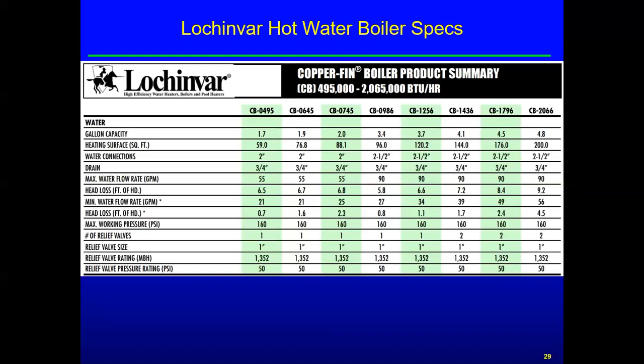Other specs from Lochinvar: head loss is what you use for sizing the pump — what's the pressure drop across the boiler? You've got all your other losses plus pushing through the boiler — about 4.5 feet of head. Maximum working pressure is 160, which matches up with the maximum for the low temperature water ASME code. Relief valve size is one inch. And interestingly, the number of relief valves is two — instead of putting a bigger one, they put two. I'd have to ask our industry contact why — maybe it's cheaper, maybe they think it's better.